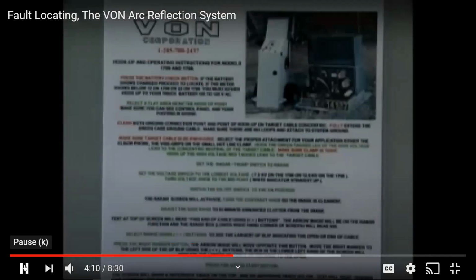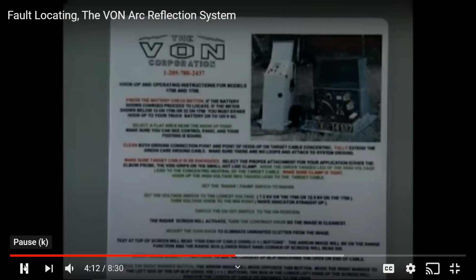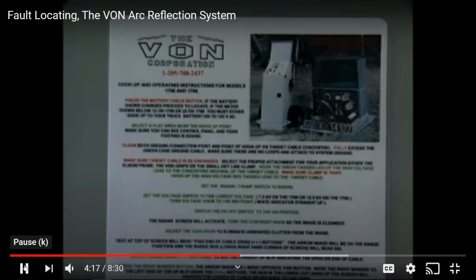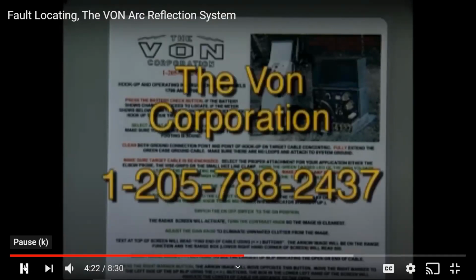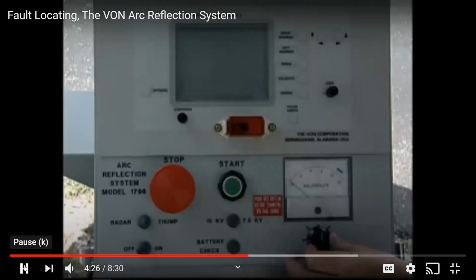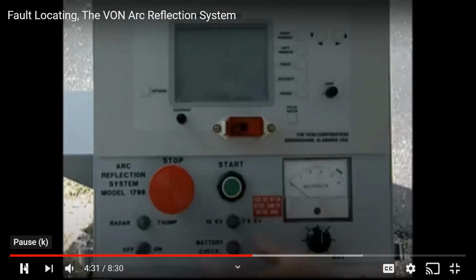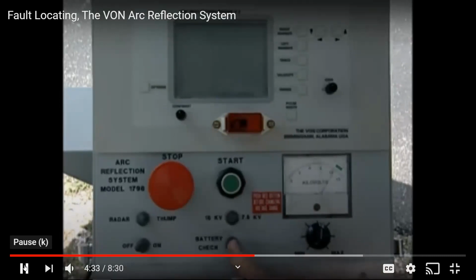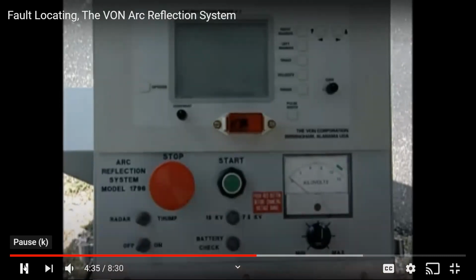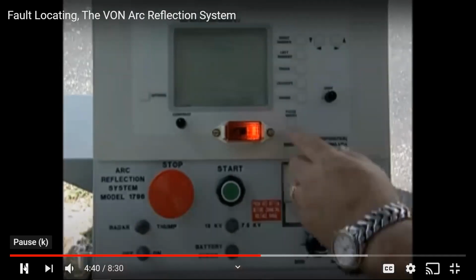The operation of the Von Arc reflective system, regardless of your model type, is essentially the same. Brief step-by-step hookup and operating instructions are located on the inside lid of the Von reflective system for easy reference, including the phone number for the Von Corporation. To begin, set the voltage indicator with the white mark up, then switch to the lowest voltage. Check the battery to make sure it's fully charged, place the machine in radar mode, and turn the unit on. The Von will then automatically find and mark the open.